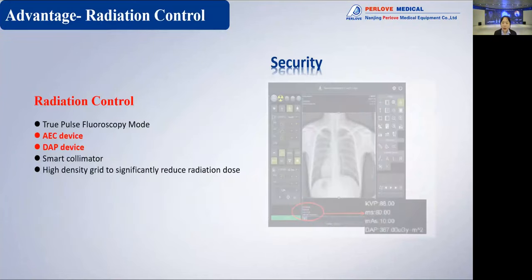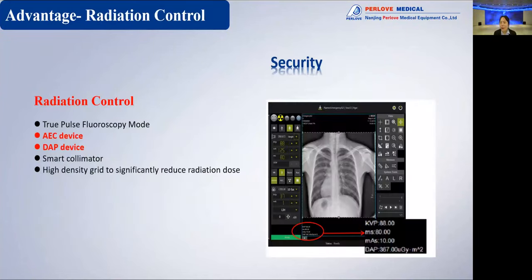And also, it is very safe. We can guarantee the security. Why? There is software to help us lower the dose. First, it is the True Pulse Fluoroscopy Mode. Second, the automatic exposure control, which is AEC device. Third, it is the dose area product device, which is DAP. All of them work as standard, and it also has smart collimator and high density grid.